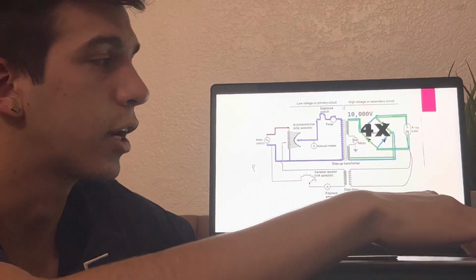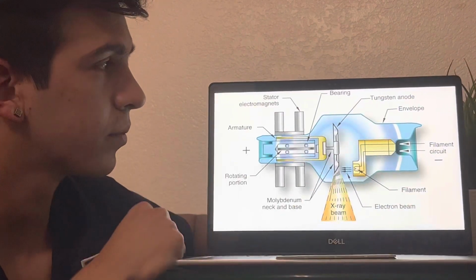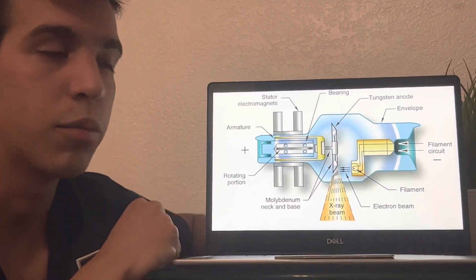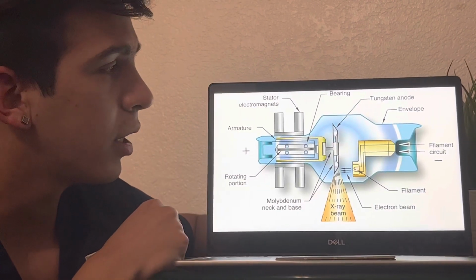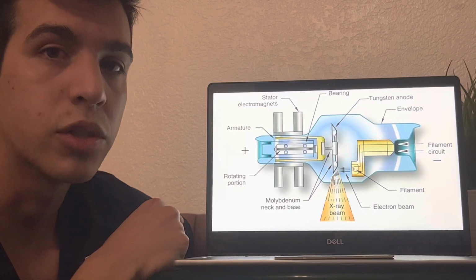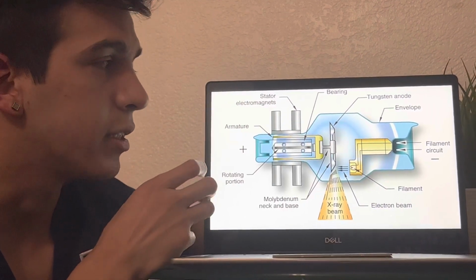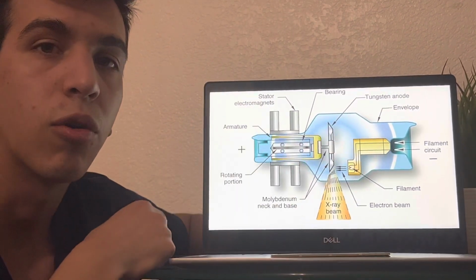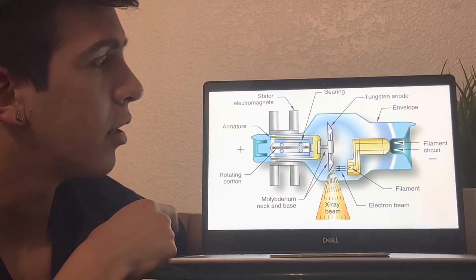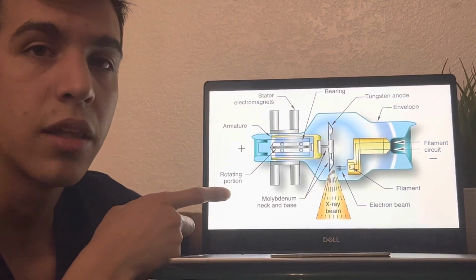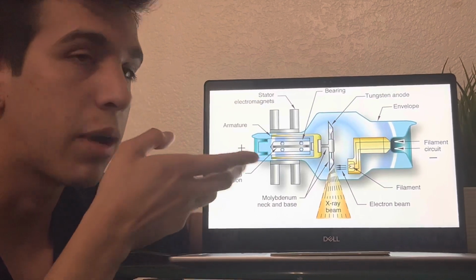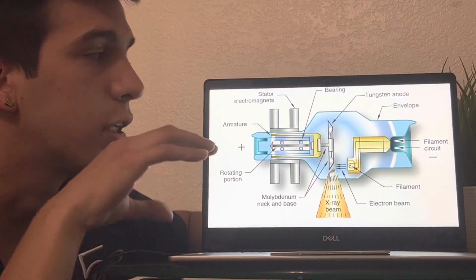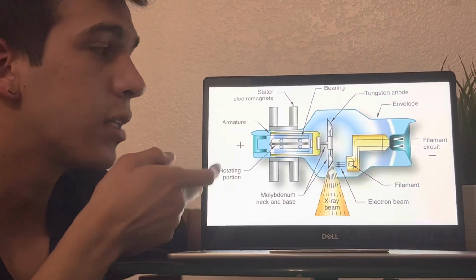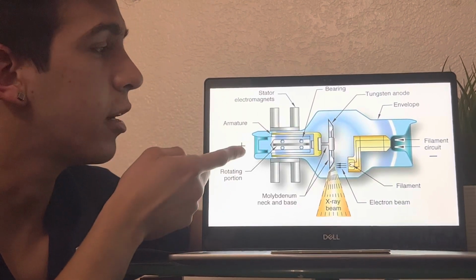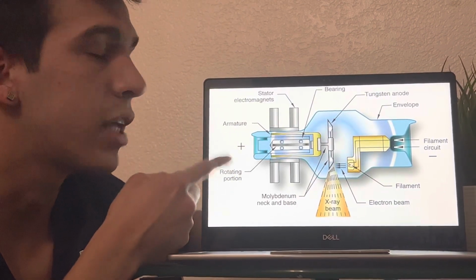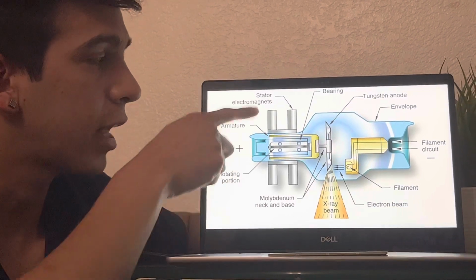4 times through the rectifiers. And then this is the X-ray tube. The X-ray tube, the majority of the components are encased inside of a Pyrex glass or metal, and that's what the envelope is. The only part that isn't going to be inside there is going to be the stator and the stator electromagnets, and that's this part right here.